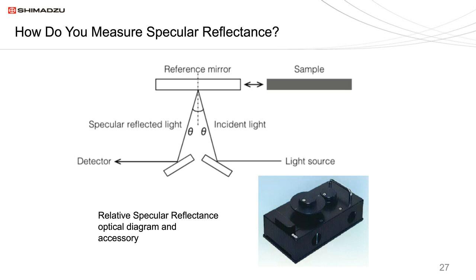Specular reflectance accessories can be either fixed angle or variable. The measurement involves placing a reference mirror on the surface for background correction, then placing your sample. Bear in mind your background correction sets the instrument to 100%, but most reference mirrors are aluminum and on the order of about 90%. To correct this, use a calibrated reference mirror where the values are known — place those values into the software and it will normalize everything to give you an absolute reflectance.